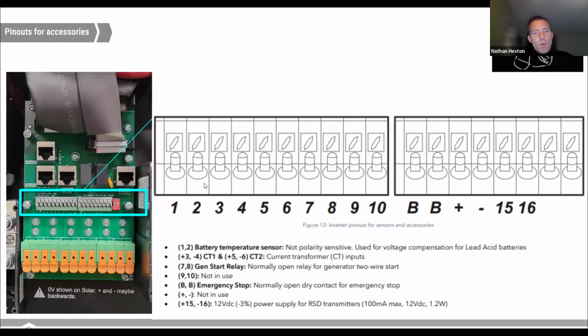And then some more pinouts here from that Sol-Ark 15k. The emergency stop, which I called 11 and 12, that's BB. It's labeled BB actually if you zoom in on the board there. So that's where you would wire your rapid shutdown. That's a normally open rapid shutdown. So when you depress that button, it closes that circuit, and then it will shut down the transmitters for rapid shutdown, pins 15 and 16. The emergency stop would also stop all output of the inverter. So the AC output of the inverter, the loads would come down with rapid shutdown.